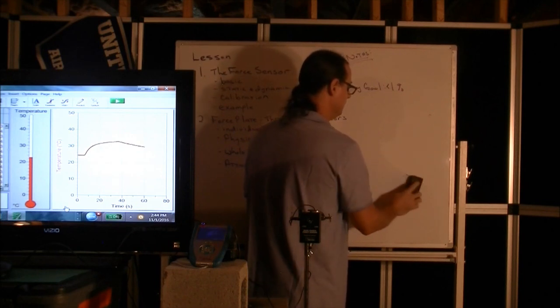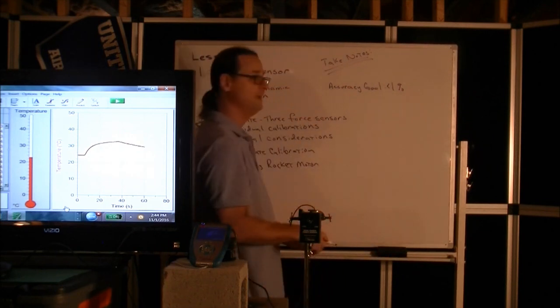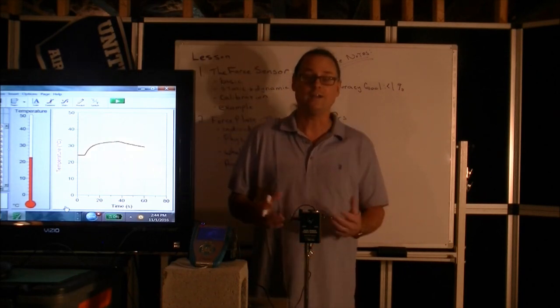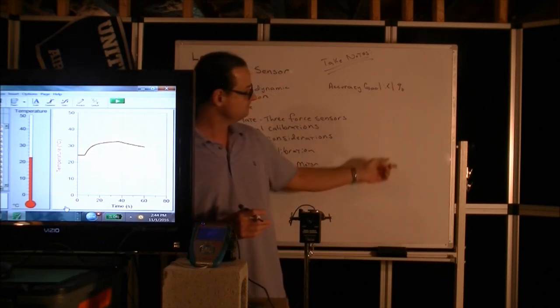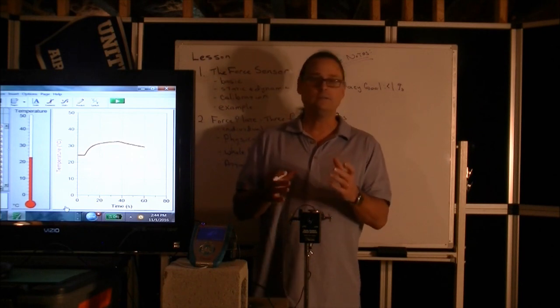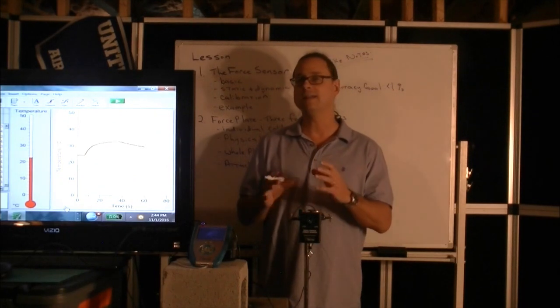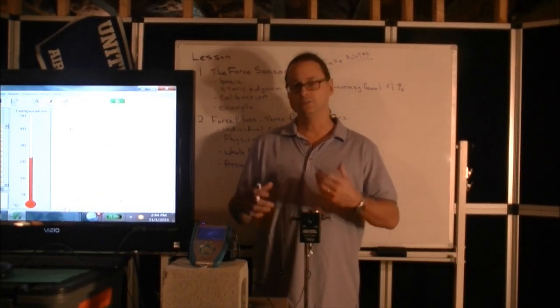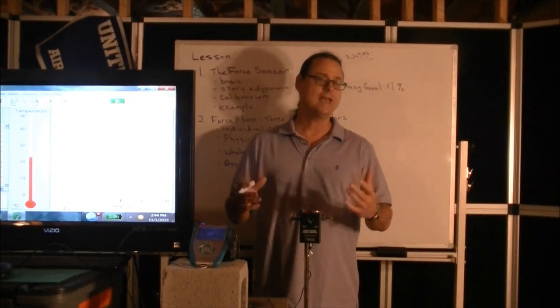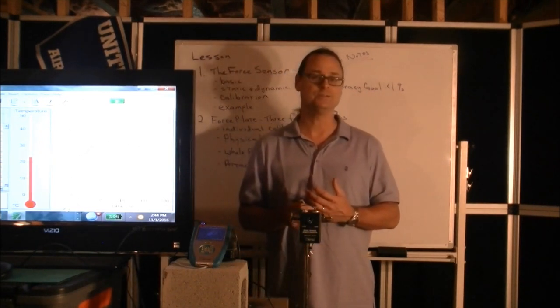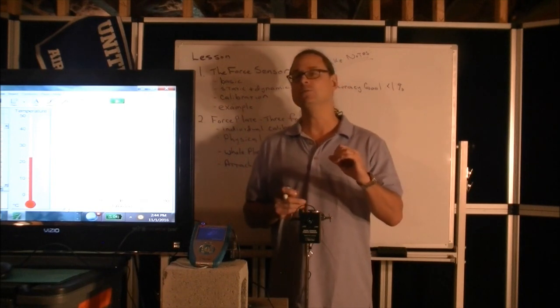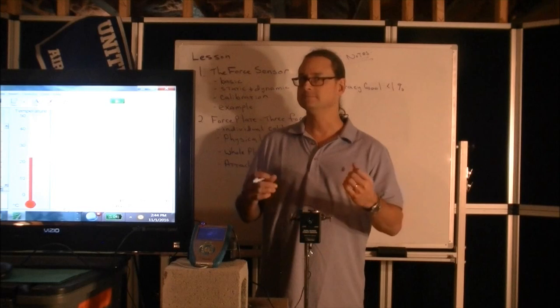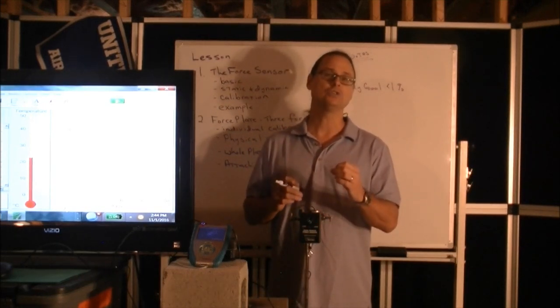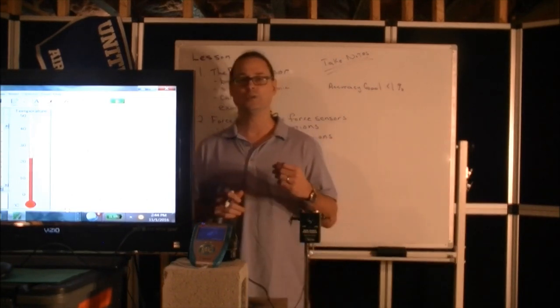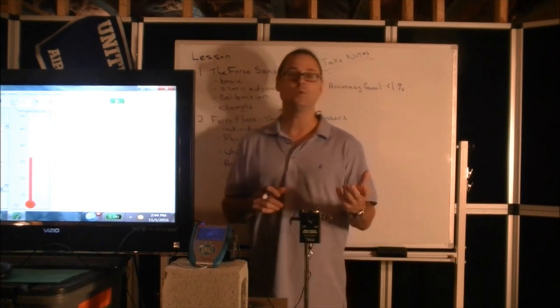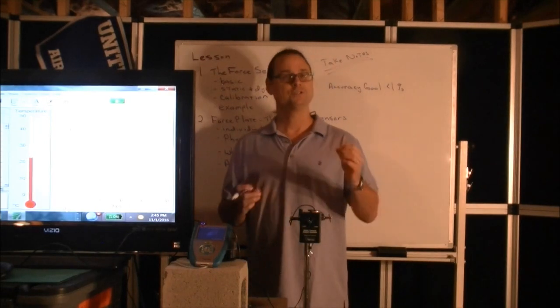You want a known good zero, you want a known good point with a known quantity, whatever quantity it is that you're measuring, and then you develop a linear scale in between. And there are a lot of tests, a little bit beyond the scope of what we're doing here, about whether or not a linear scale is very good. You can kind of take our word for it here that with the force sensors you can get to better than 1% accuracy in the force measurements if you use a linear scale, as long as you keep in mind that when you're calibrating it, the full scale that you're calibrating to is close to the actual force that you're trying to measure. For example, if you're measuring rockets with a peak force or peak thrust of 10 to 20 newtons, you want your calibration to ultimately be somewhere between 10 and 20 newtons.